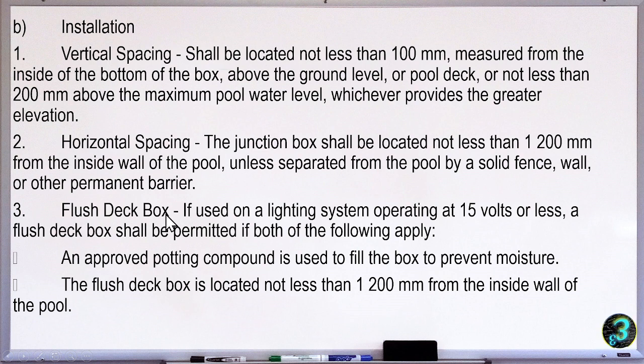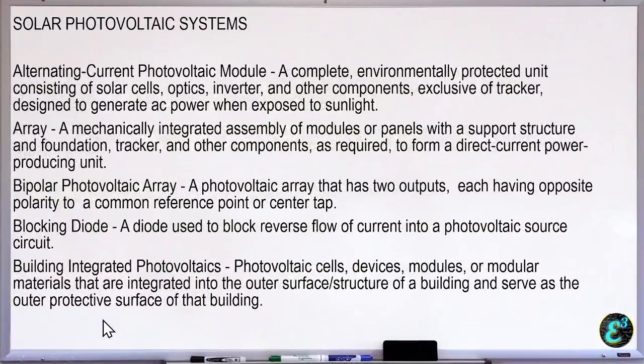Then, flush deck box, no, yung ating mga box na naka-flush doon sa ating wall, no, or sa wall ng ating tawag doon sa pool or doon sa mismong pathway. If used as a lighting system operating at 15 volts or less, a flush deck box shall be permitted if both of the following apply. An approved potting compound is used to fill the box to prevent moisture. So, dapat yung ating box is watertight. No? Waterproof so that the moisture could not enter. The flush deck box is located not less than 1,200 mm from the inside wall of the pool. Then we go next to solar photovoltaic system.